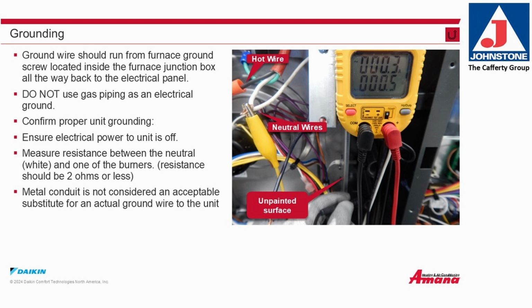Electrical grounding. A ground wire should be run from the furnace ground screw located inside the furnace junction box all the way back to the electrical panel. Do not use gas piping as an electrical ground. Confirm proper unit grounding. Ensure electrical power is turned off. Measure resistance between the neutral, typically the white wire, and one of the burners. Resistance should be 2 ohms or less. Metal conduit is not considered an acceptable substitute for an actual ground wire to the unit.